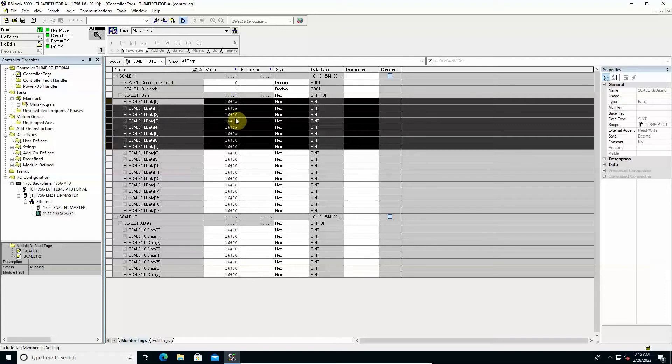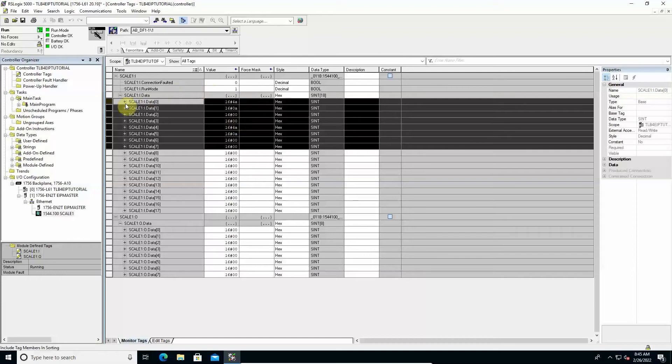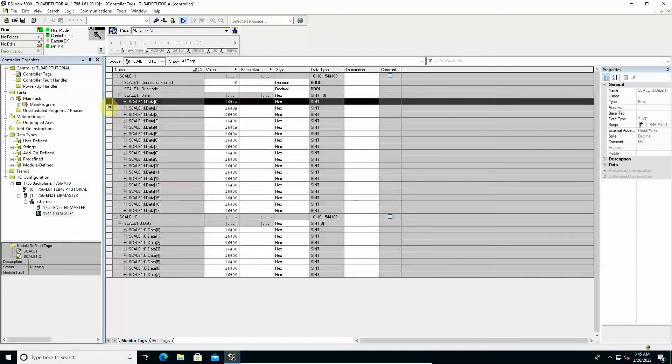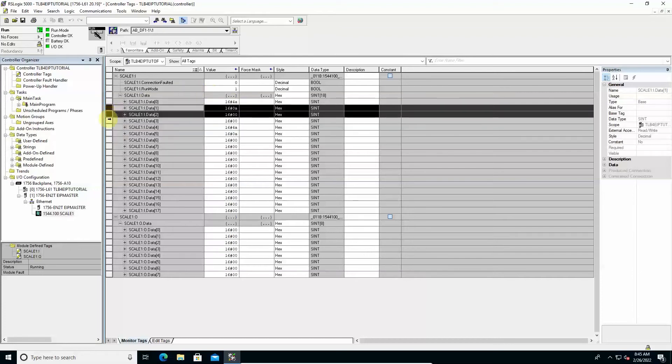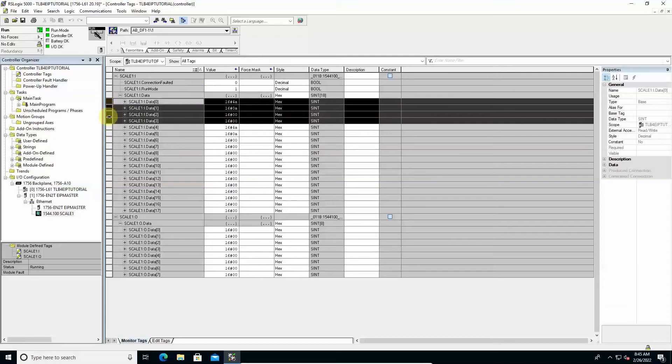In the case of Ethernet IP, the order in which the bytes are published by default is Little Endian. Therefore, the bytes of lower value are first. At this moment, for example, for the gross weight value, the lower value bytes are 4A and 0A.